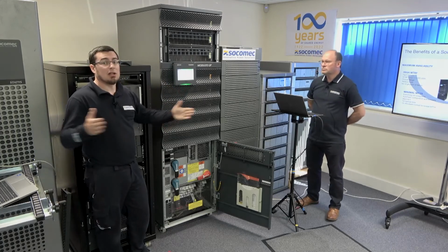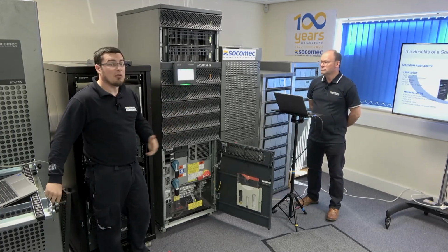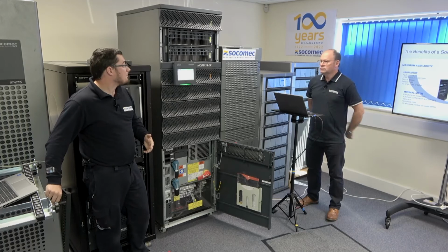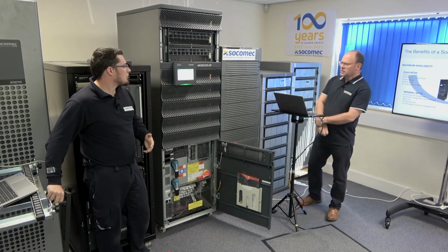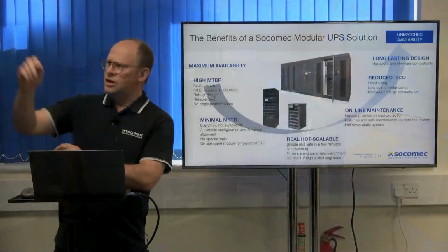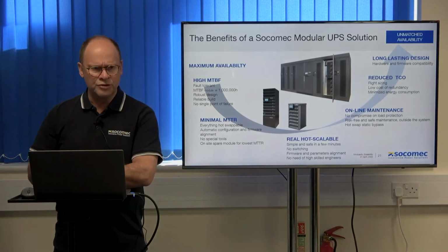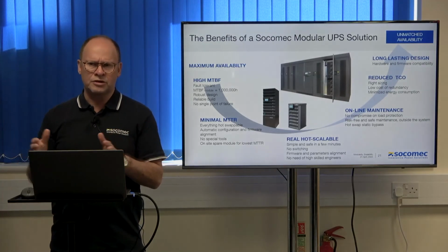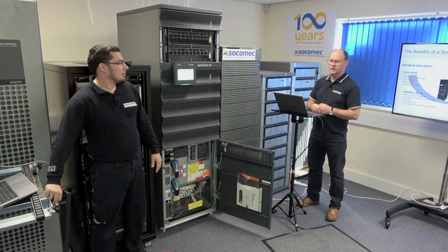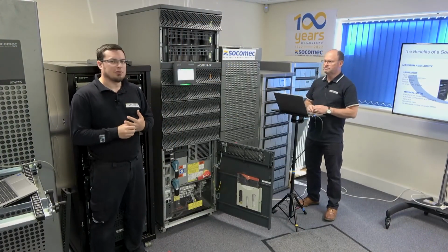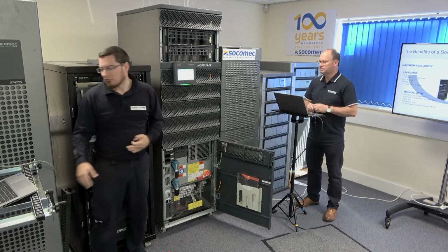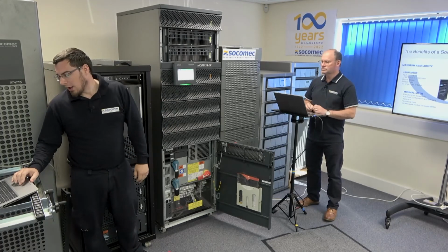So you do need a small amount of space, about 400 mil at the back of the machines. And there are options for top entry. There's an option at the back for a top exhaust. So it's I think 200 mil. So instead of needing 400, you only need 200, and it's a chimney up the back with exhaust fans on the top. A couple of fans on top as well. But so then you can push it right back and regain that space as well.